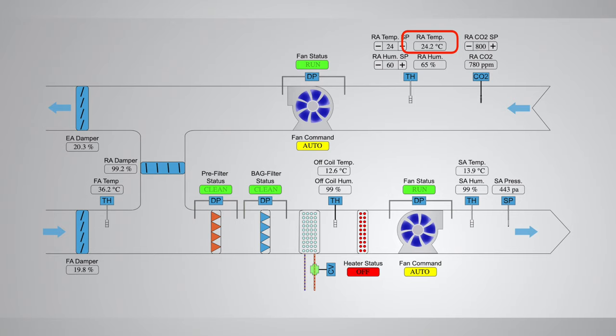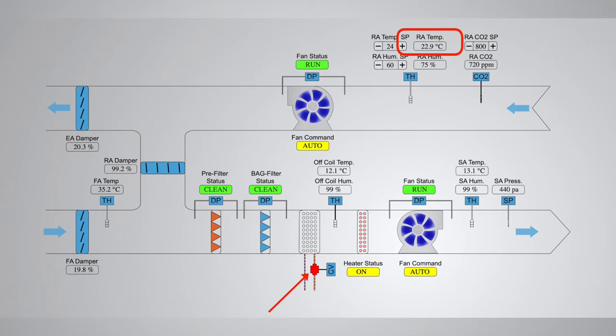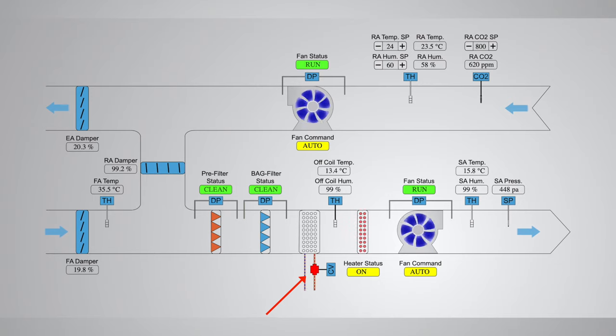This results in cooling the space more, bringing the return air temperature down. The cooling coil will be modulated until the return air temperature matches the set point. Once the set point is achieved, or the return air temperature is nearing the set point, the control valve will start to close until the return air temperature is within the design set point. If the return air temperature falls below the set point, the chilled water control valve will be fully closed. If the return air temperature remains less than the set point even after the control valve is fully closed, then the electric heater will be switched on to maintain the space temperature until the return air temperature and set point match.